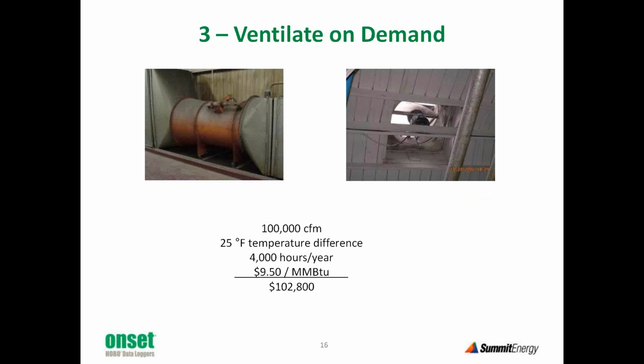So I'm ready to move on to number 3, ventilate on demand. One of the easiest ways to reduce energy usage is to stop bringing in so much outside air. In the old days, we designed for a minimum CFM, a minimum volumetric flow per person based on maximum occupancy in a facility. That doesn't apply to factories, and it's just not the best approach anywhere. Even if we think, for example, of a large office building, the reason you bring in outside air is because people convert oxygen to CO2.